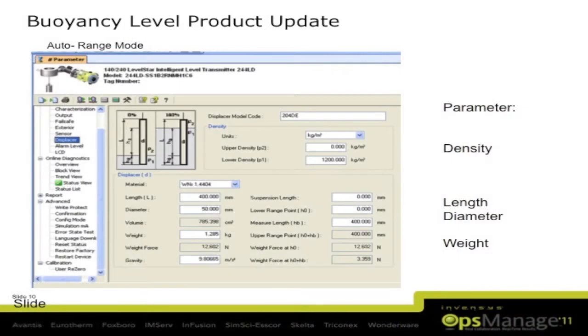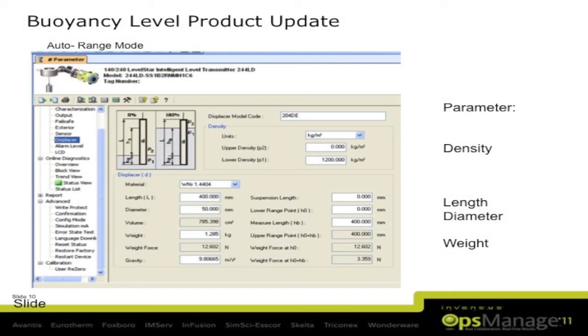And for this we have a DTM page. You can enter this data in a very easy way, in a logical way. The upper field is the density, lower and upper density. You type this in. So it's very easy now if the process changes, if the user is using several batches with several parameters, you can download the new density from the DCS system. This is on the density area.